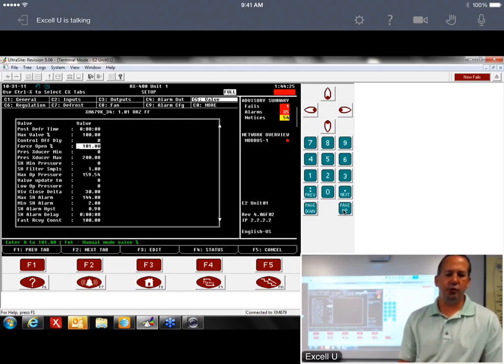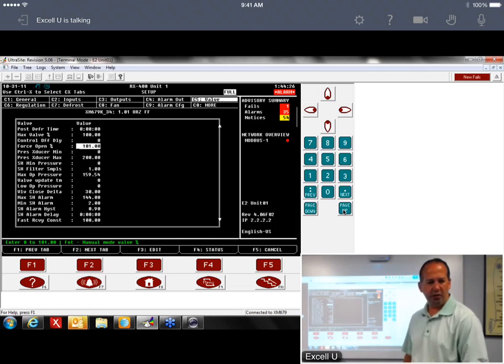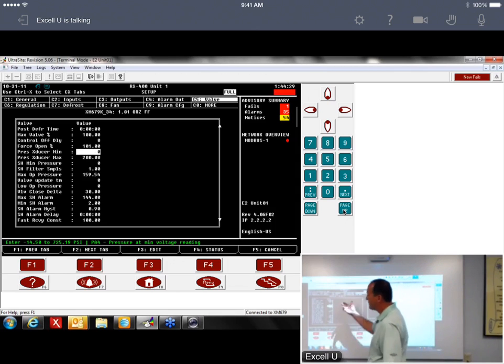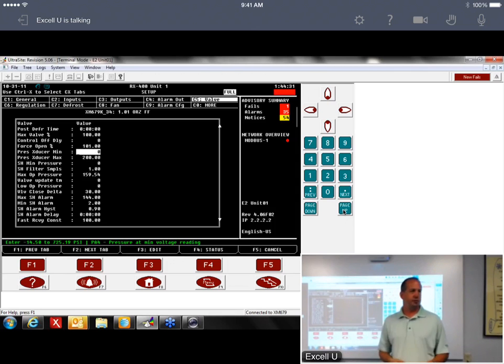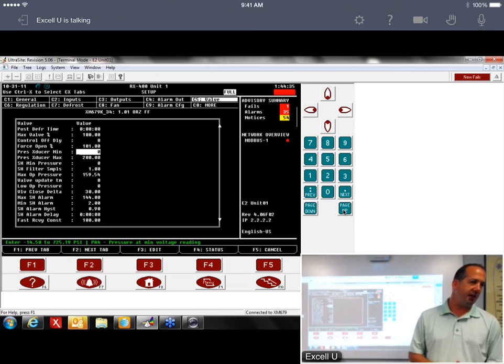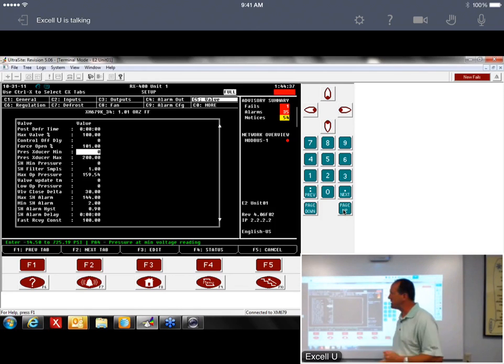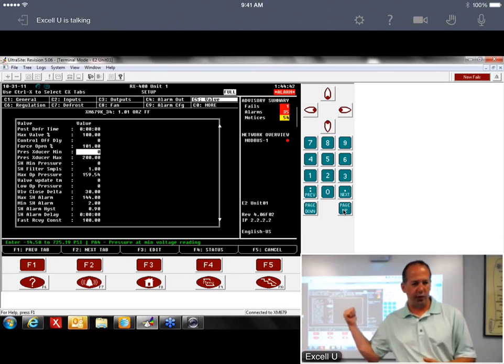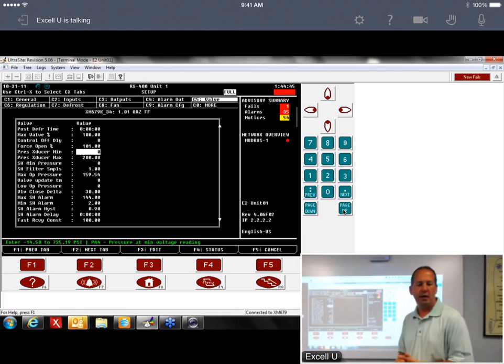So in the E2, we default to 0 and 200. We use 200-pound transducers. If you had to change a transducer, all you had on your truck was a 500-pound transducer, you can use it. You just got to come in here and you got to set that to 500 pounds for the scaling. But you can use it. That's where you'd set it. Again, it's in the valve tab.